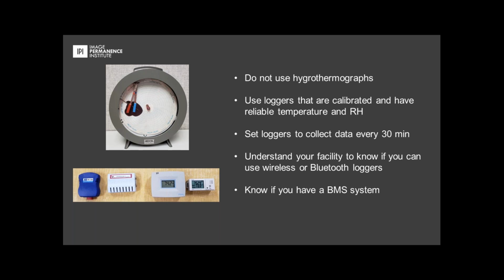That means having loggers that are calibrated, and we've come across a few that are sold that aren't calibrated. You're just getting what they have, and it's rare, but there are a few out there. But it's more the reliable temperature and relative humidity. Some sensors aren't as accurate. So when you're making that decision, you want to try and get a logger that has an offset for the temperature and relative humidity that's as small as possible.